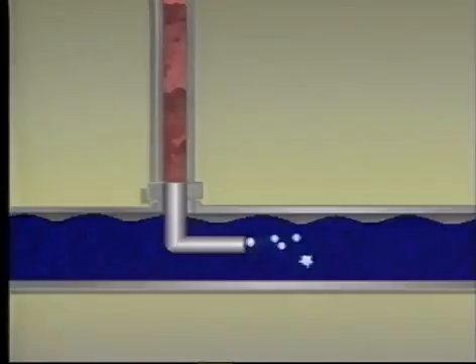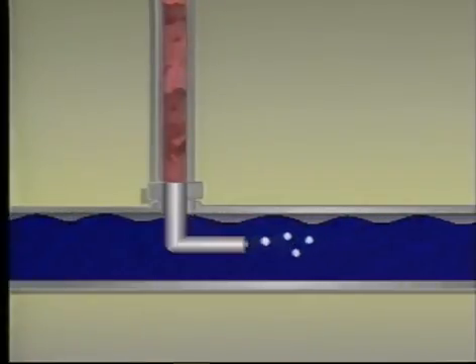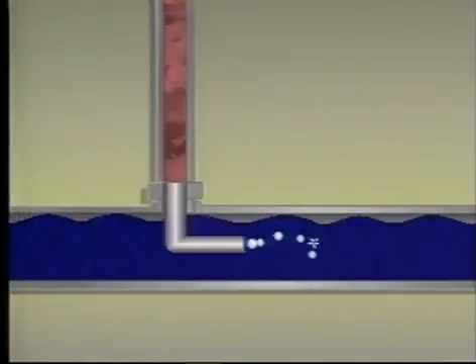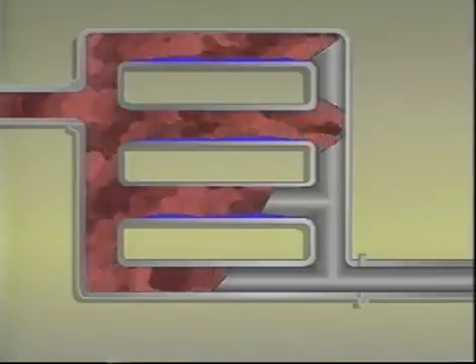If flashing condensate must be discharged into a cool condensate line, it should be discharged in the direction of condensate flow and away from the pipe wall. Precautions must be taken that heat exchanger tubes are always filled from the supply end only.